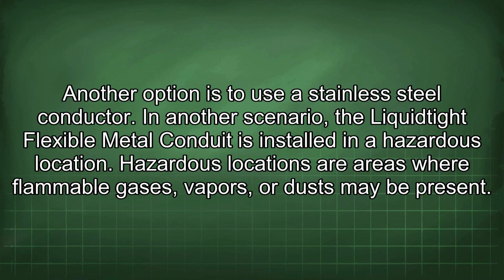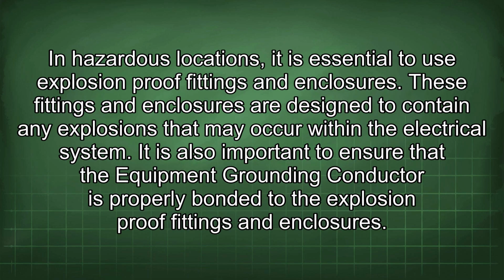In another scenario, the Liquatite flexible metal conduit is installed in a hazardous location. Hazardous locations are areas where flammable gases, vapors, or dust may be present. In hazardous locations, it is essential to use explosion-proof fittings and enclosures. These fittings and enclosures are designed to contain any explosions that may occur within the electrical system. It is also important to ensure that the equipment grounding conductor is properly bonded to the explosion-proof fittings and enclosures.